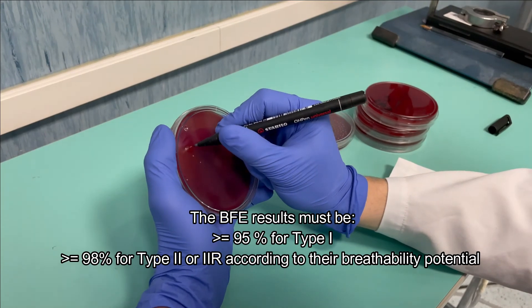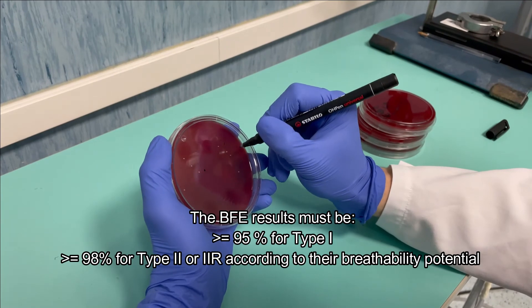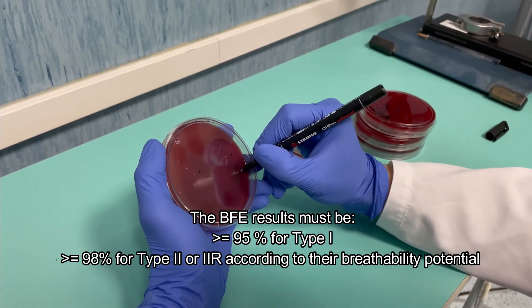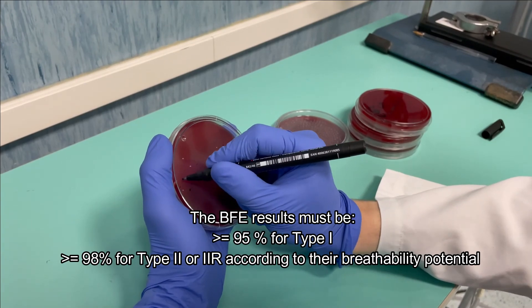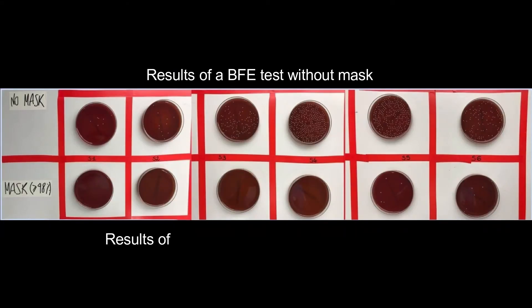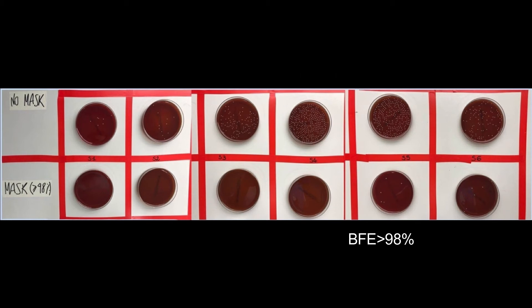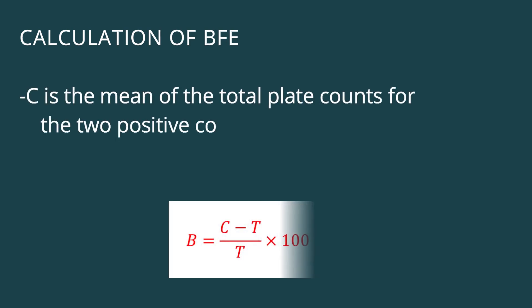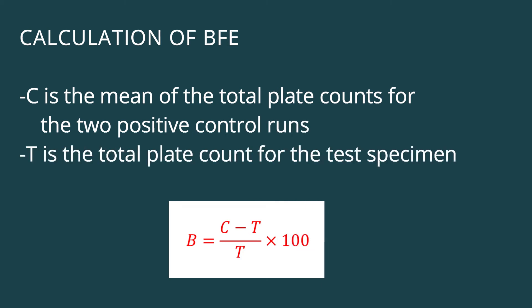The BFE results must be greater than or equal to 95% for Type 1, and greater than or equal to 98% for Type 2 or 2R, according to the breathability potential. Results of BFE tests without masks and results of BFE tests on masks with BFE greater than 98% are shown. Calculation of BFE: C is the mean of the total plate counts for the two positive control runs; T is the total plate count for the test specimen.